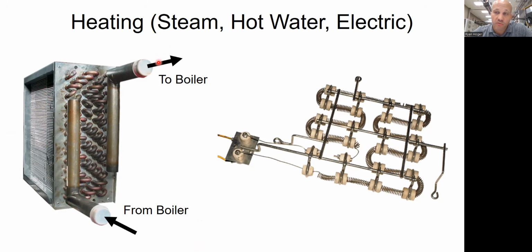Now, just looking at it won't necessarily tell me if it's a hot water or a steam coil. I'm going to have to look at other things, like is there a trap on it, or go look at the boiler itself. But in either case, if it's hot water or steam, from a heat pump replacement standpoint, that answer is going to send me down one path. If they have hot water or steam, my heat pump decision is going to be the same. If they have electric resistance heating, I'll have a heater like this, like we saw on all the other stuff, and that's going to be a different answer for heat pump.